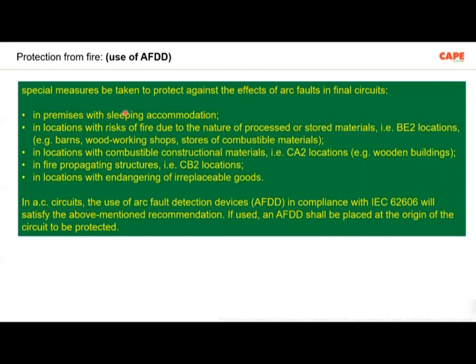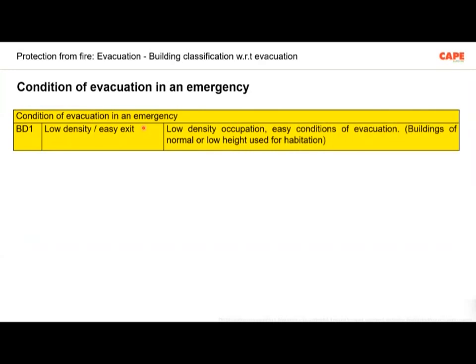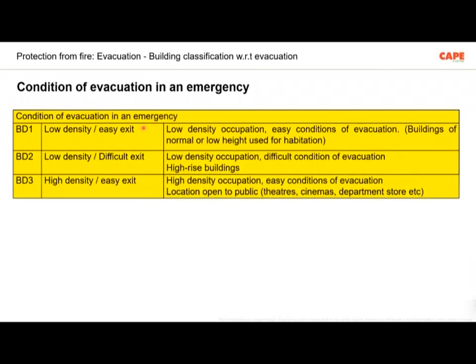Mounting is important. Special protective devices such as arc fault detection devices are being recommended in the upcoming National Building Code, especially for premises with sleeping accommodation. That means the bedrooms or the hotel rooms. And in special cases, not everywhere, but in some places, you need additional safety measures such as arc fault detection devices. Today we advertised that we will be discussing more about the condition of evacuation in an emergency, which is very, very important. So in case of a fire or an emergency situation, what are the conditions which the electrical system should satisfy in order to evacuate people from the fire?